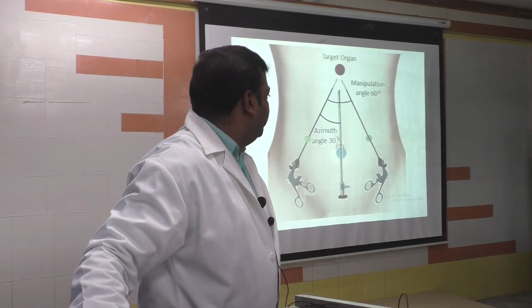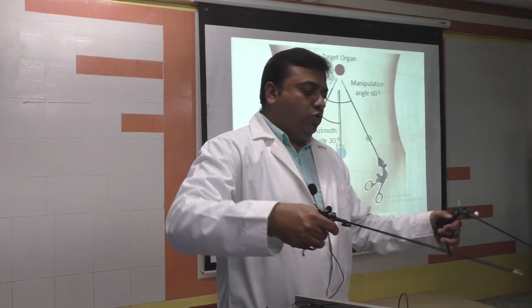So some books will be wrongly saying that azimuth angle is half of manipulation angle. That is not right. Manipulation angle is between these two instruments, and this 60 degree should be equally distributed, 30 degree on one side, 30 degree on other side. Some people maintain this 60 degree, but between this central optical axis and working port it will be some 30 degree, here it will be 90 degree. So that should not be there. This 60 degree should be equally divided 30-30. You should not make it 15 or 45 or 10-50 or 25-35, that should not be there.